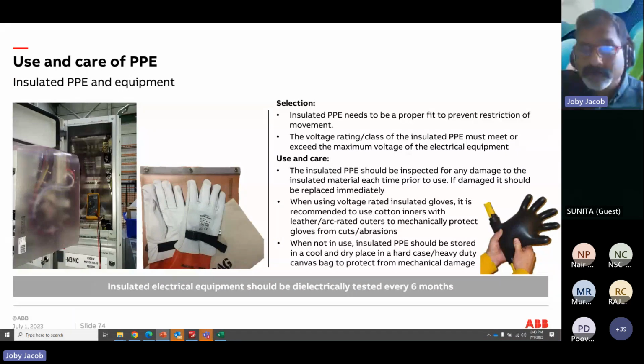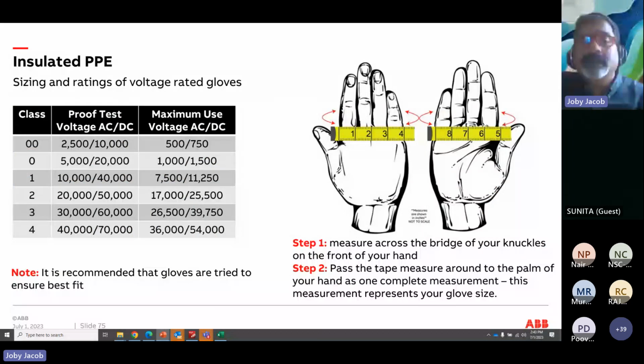Gloves are always like life-saving equipment. When you use the gloves, you also use a leather protector. Leather is a natural arc retardant, and it's mechanical protection also. Before you start using the gloves, you test them. You can even measure the gloves according to your palm size. Get the right gloves as per the class, from class 00 up to class 4. You can get from 500 volts or 750 volts DC up to 36,000 volts, or up to 54,000 volts DC.